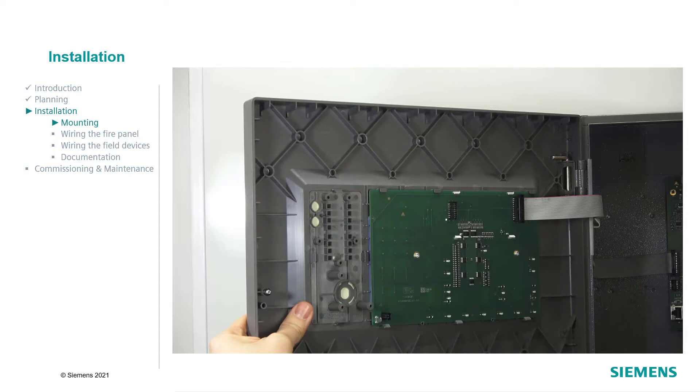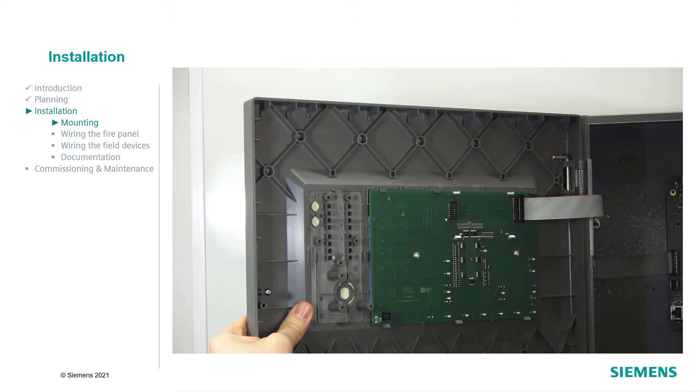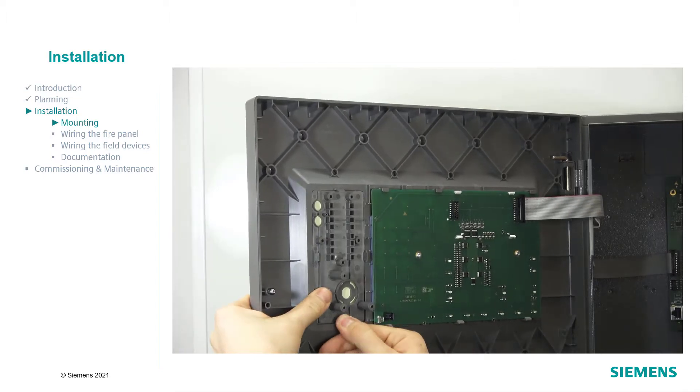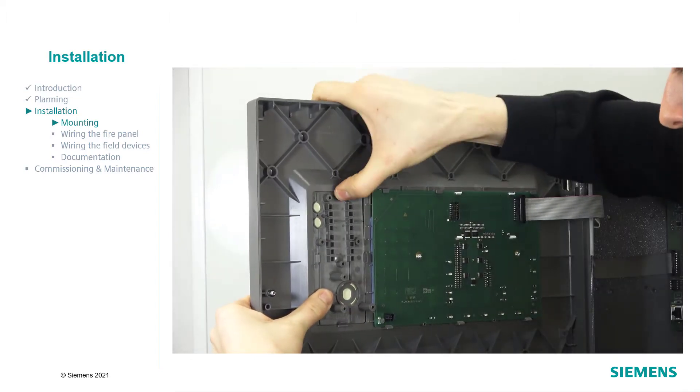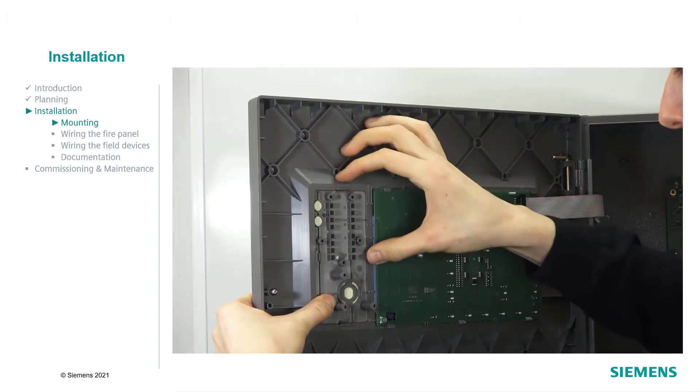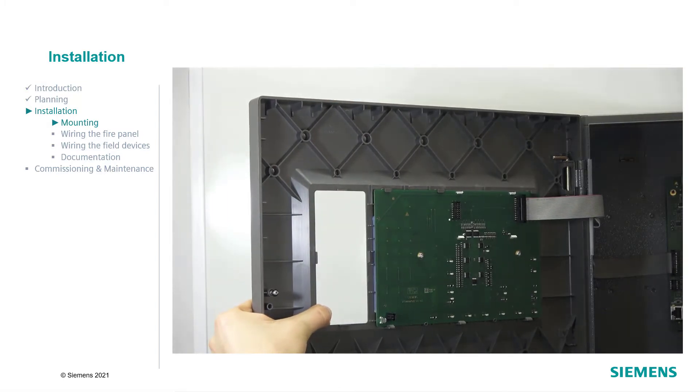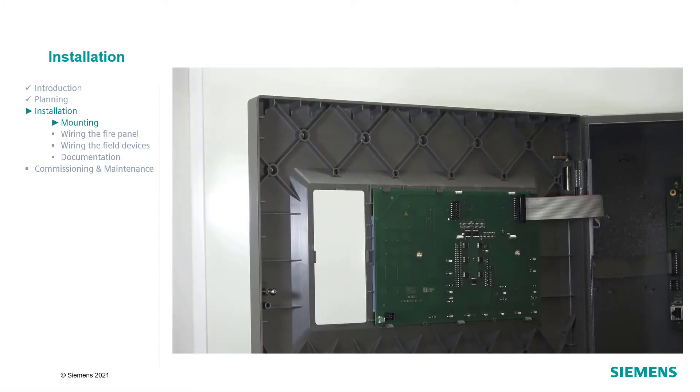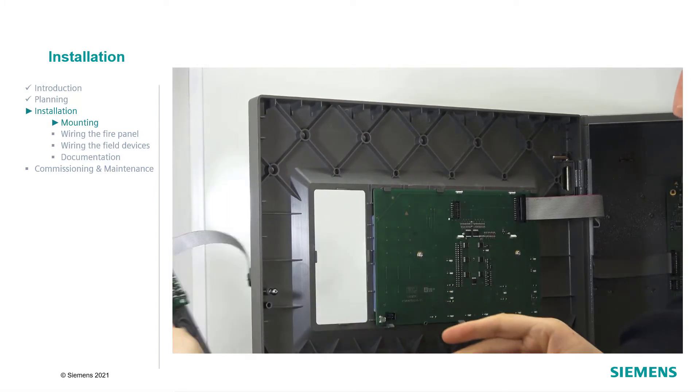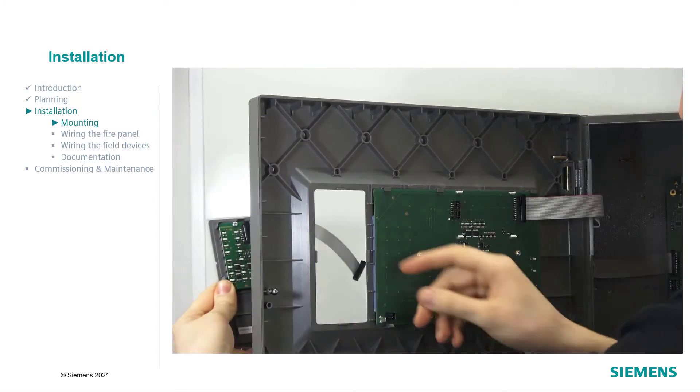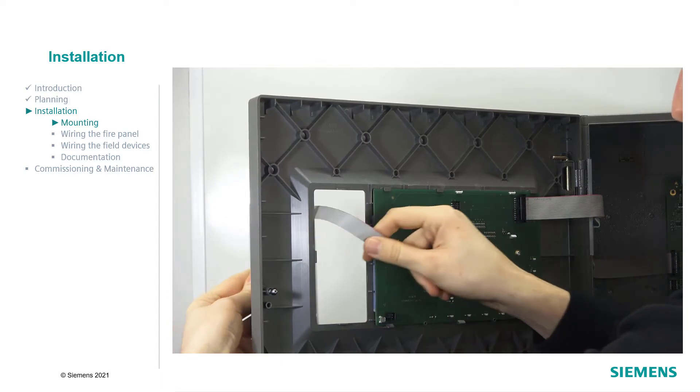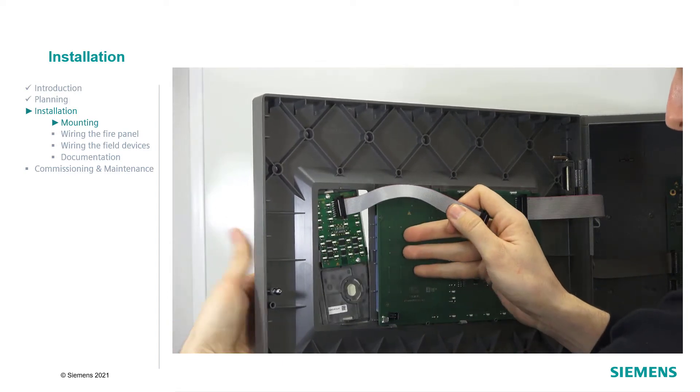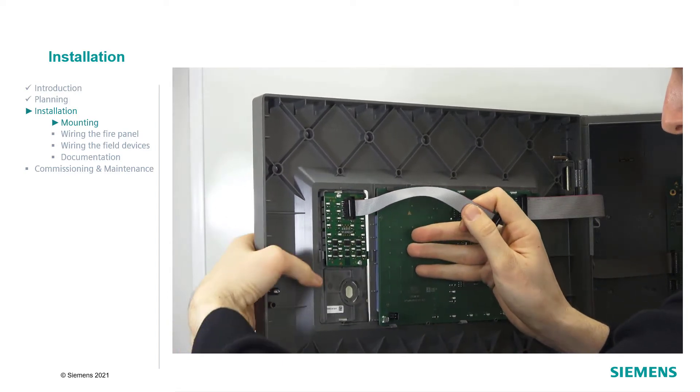Now, we would like to show you how to mount the accessories. The evacuation module, the LED indicator and the key switch are mounted the same way. Detach the blank plate by lifting the four clamps and push it off the person-machine interface, also called PMI. Insert the new module by pressing it firmly into the slot of the PMI until it clips in place.